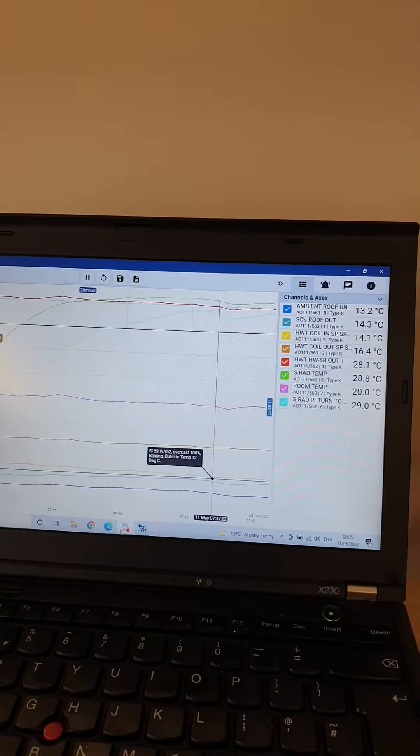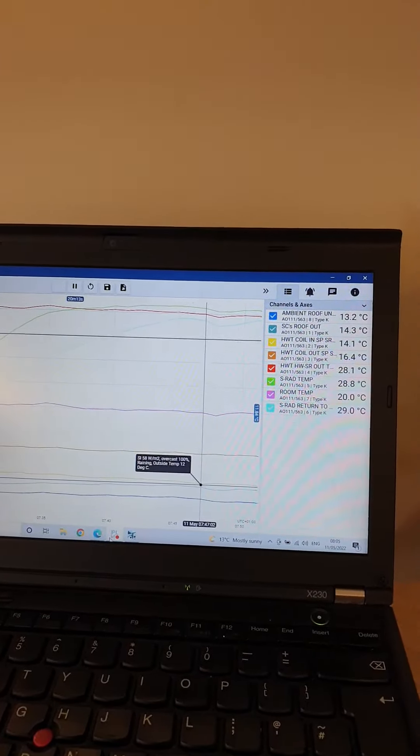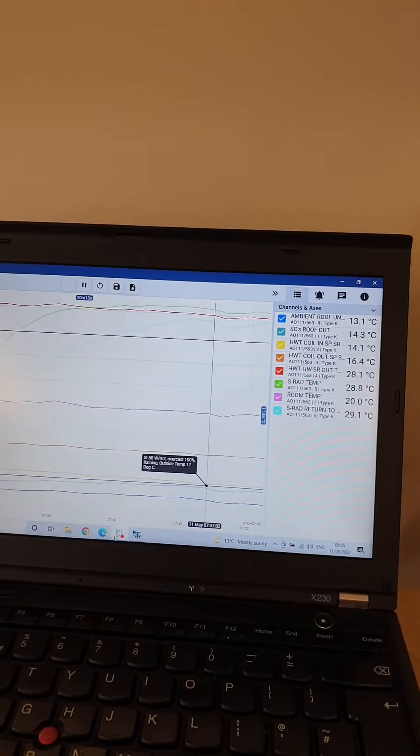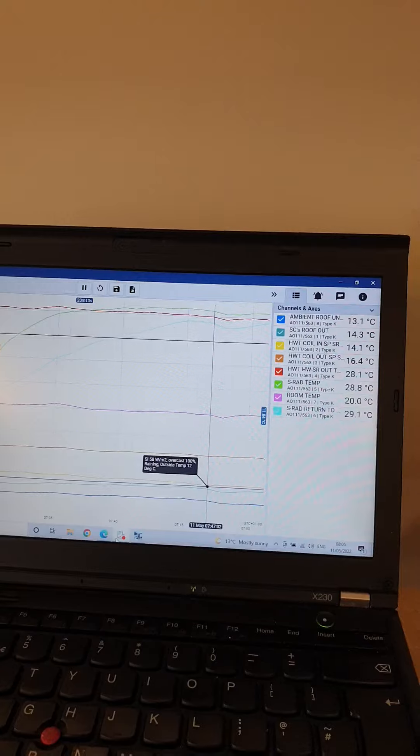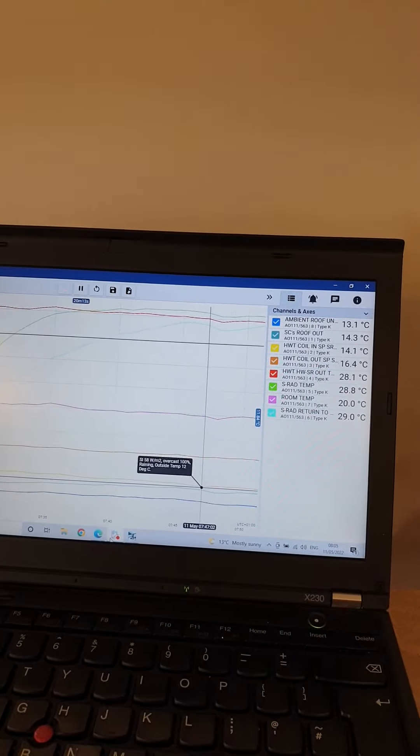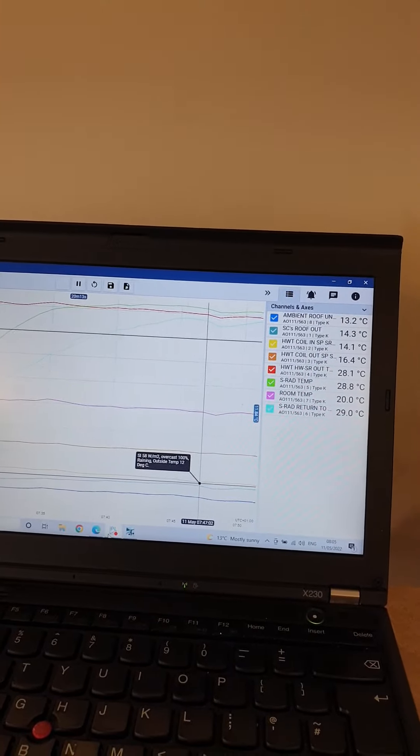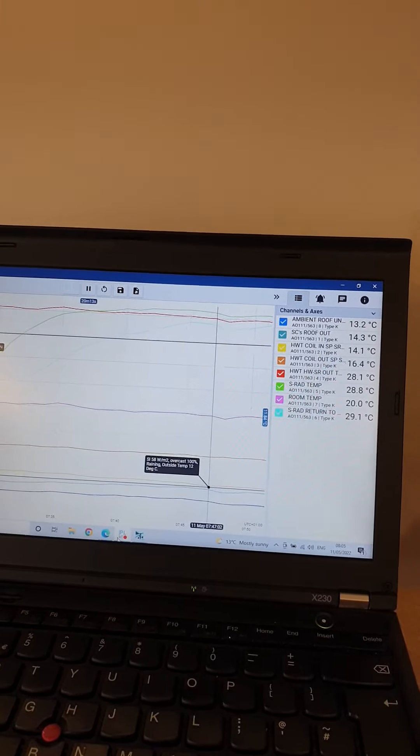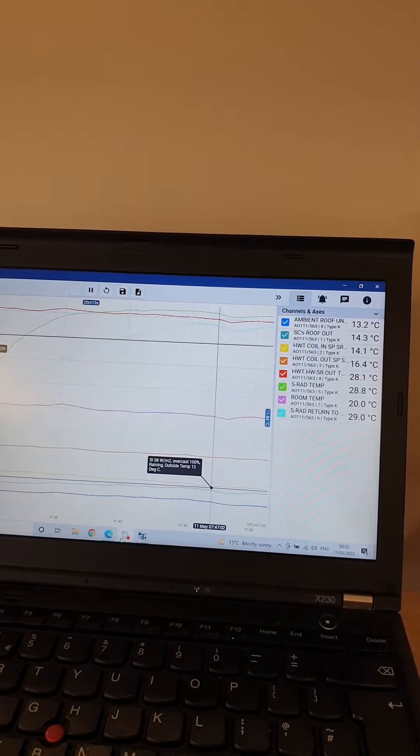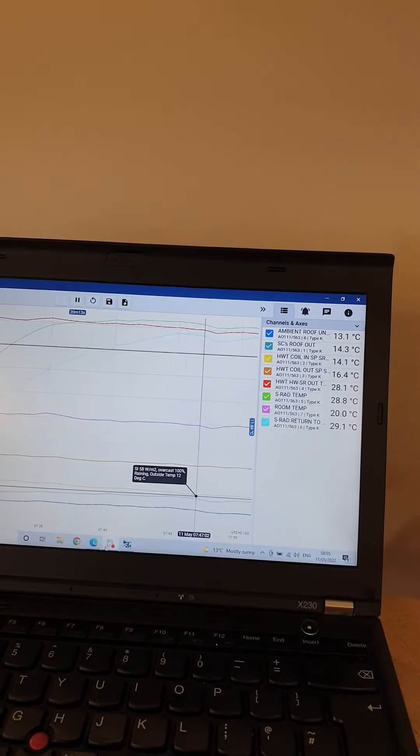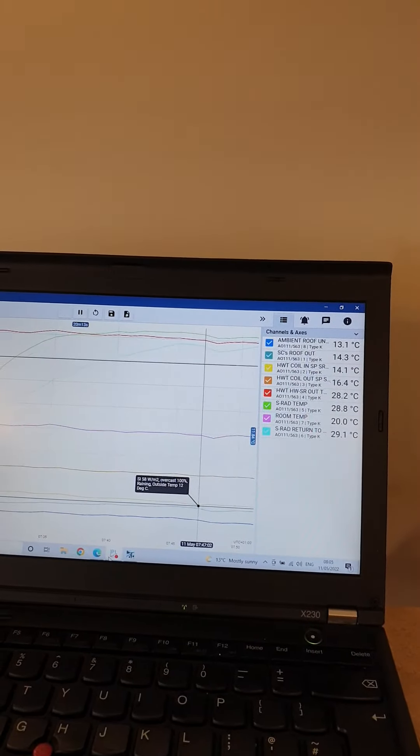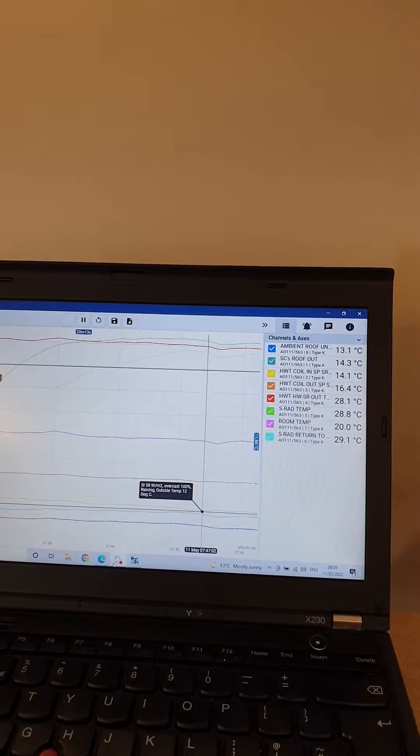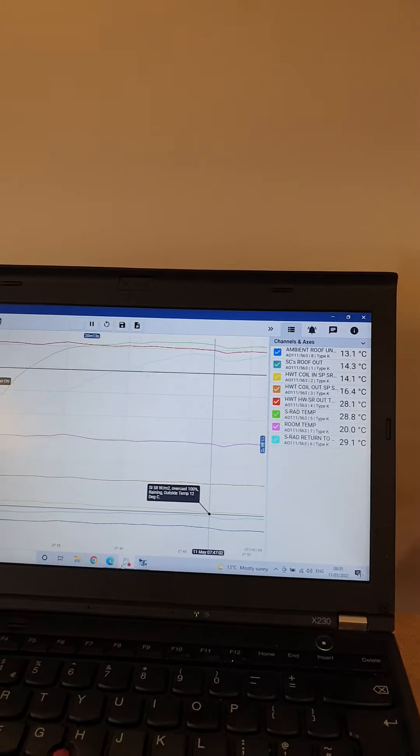The temperature of the radiator itself is at 28.8 degrees at the minute. The room temperature is at 20 degrees, and that's been creeping up from about 17 degrees since 7:30 this morning. So a nice steady state with a nice temperature difference. The radiator is working really well.